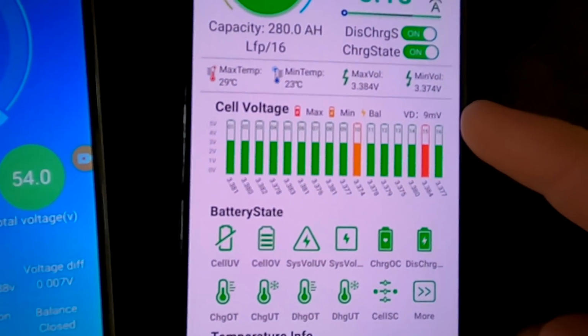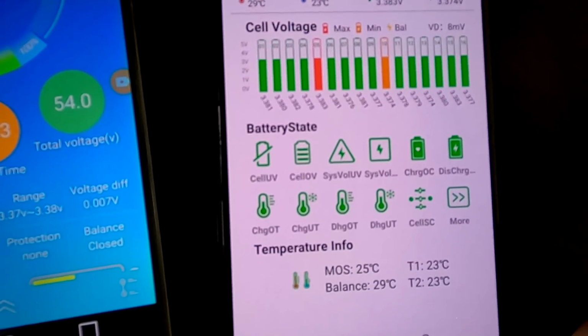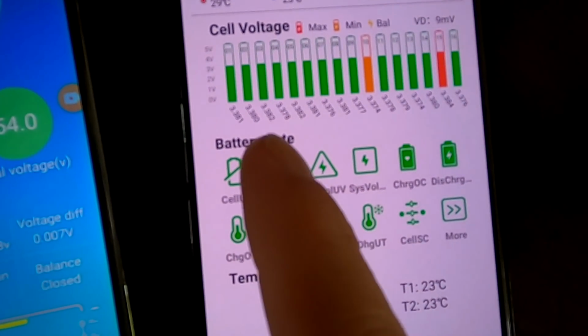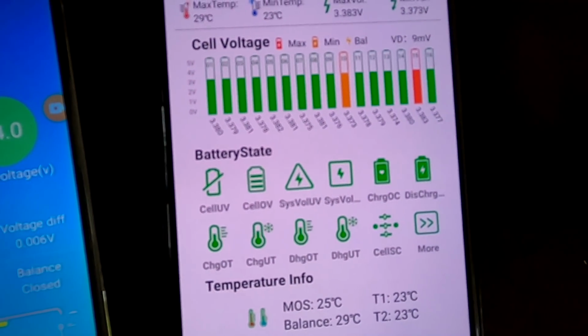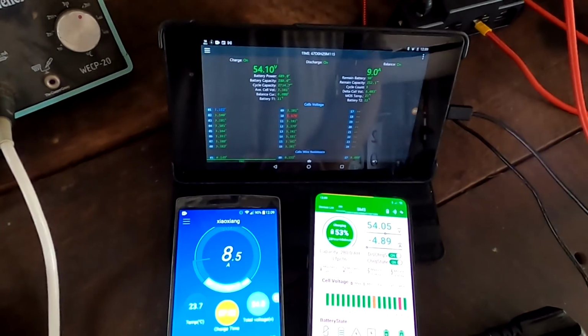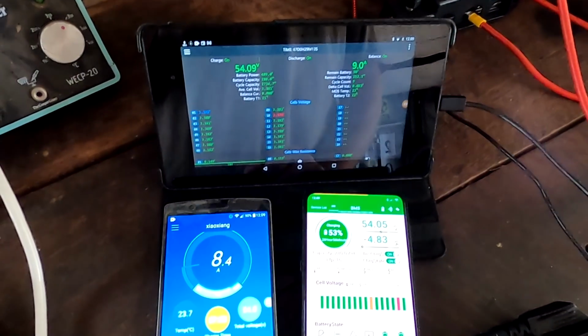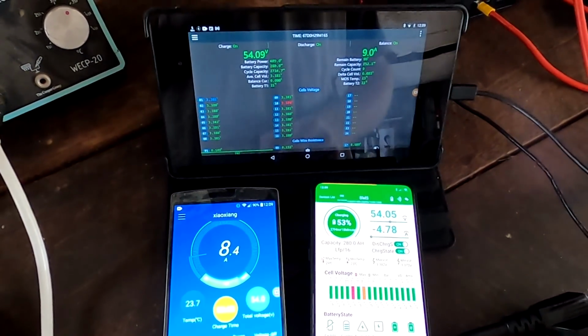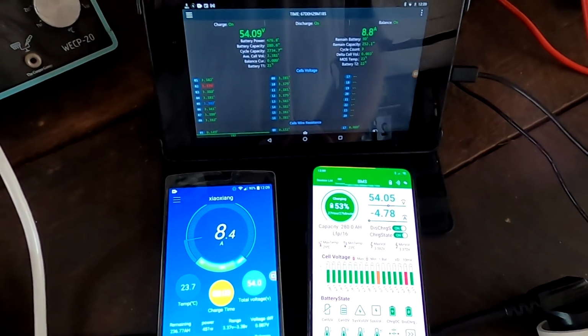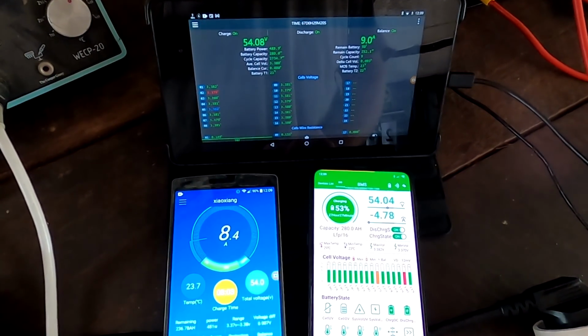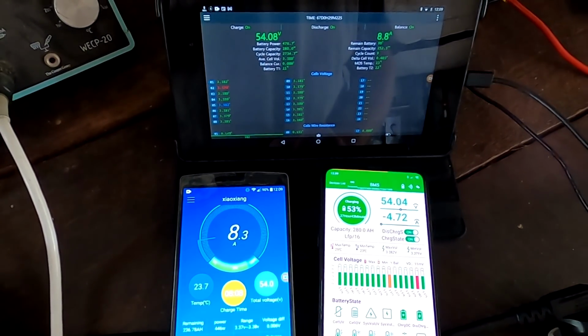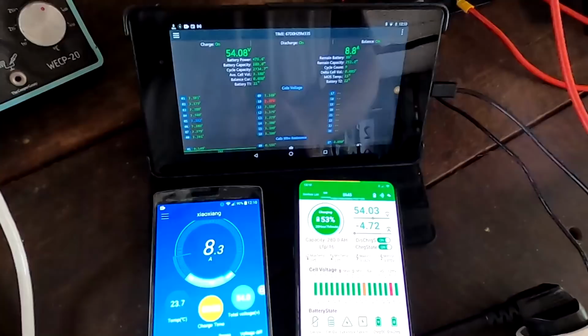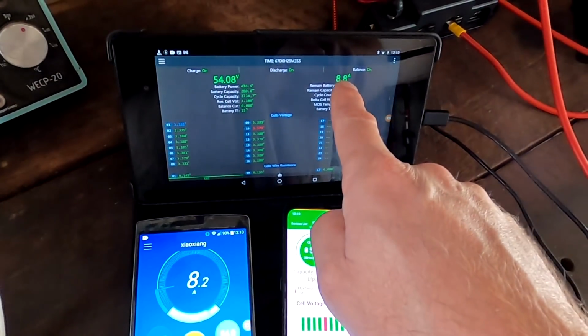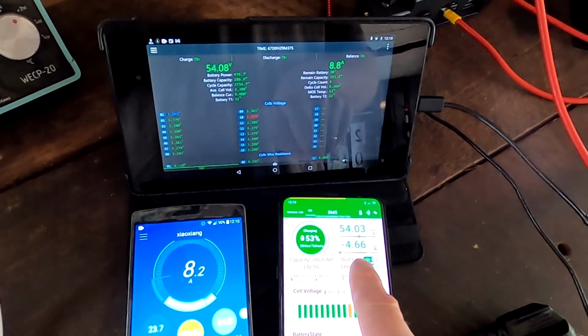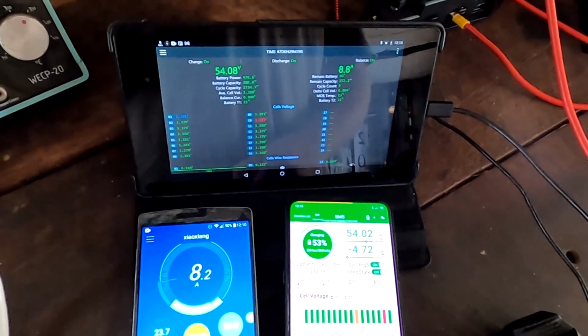We can recalibrate this current sensor. Anyway, we've got a 9 millivolt deviation across the whole 16 batteries and 3.38 volt as well, so it seems like all 3 battery banks are fairly stable and voltage-wise the same. But as we know, this doesn't mean anything with lithium iron phosphate batteries, right? You can see 8 amps, 8 amps, 4 amps only, which is not correct.